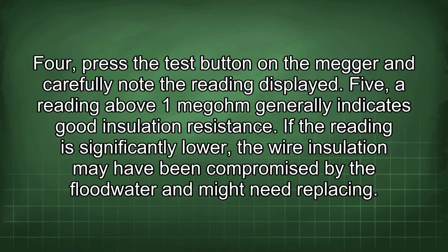4. Press the test button on the Megger and carefully note the reading displayed. 5. A reading above 1 megohm generally indicates good insulation resistance. If the reading is significantly lower, the wire insulation may have been compromised by the floodwater and might need replacing.